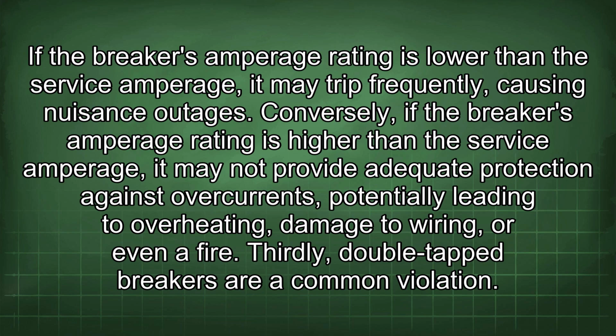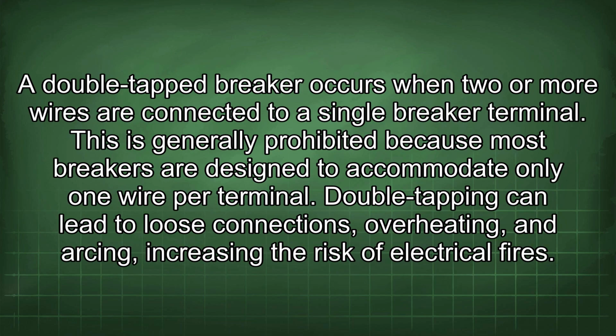Thirdly, double-tap breakers are a common violation. A double-tap breaker occurs when two or more wires are connected to a single breaker terminal. This is generally prohibited because most breakers are designed to accommodate only one wire per terminal. Double tapping can lead to loose connections, overheating, and arcing, increasing the risk of electrical fires.